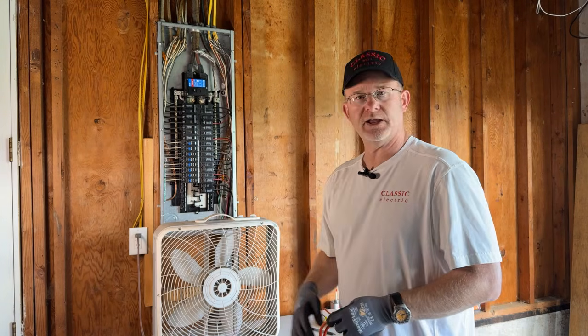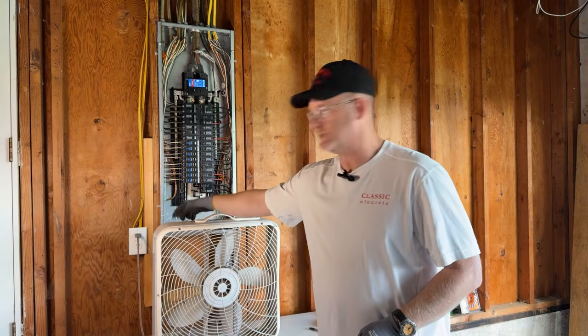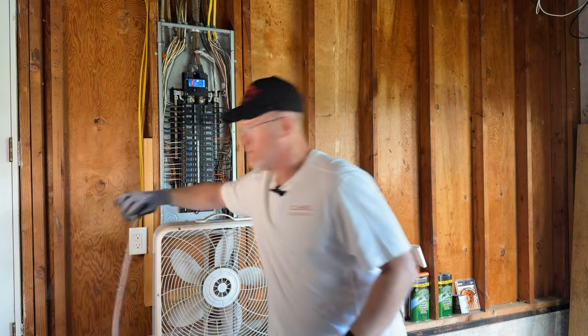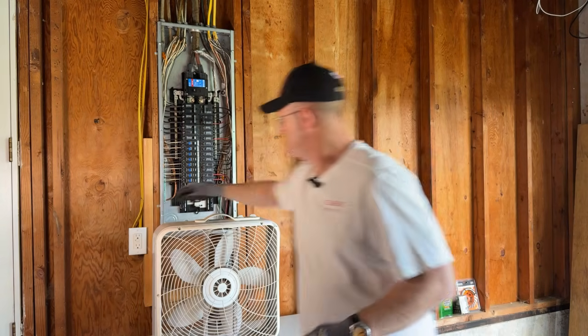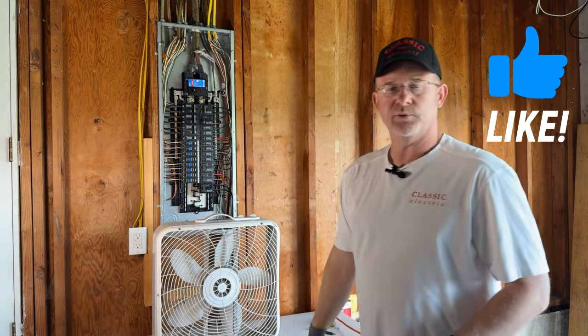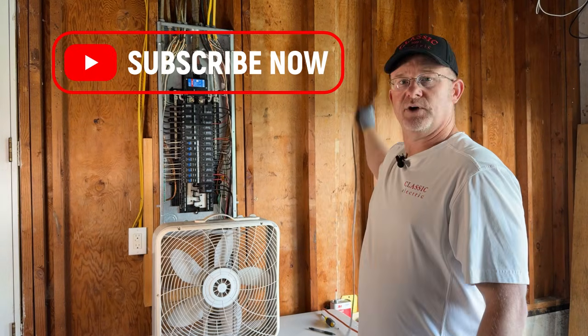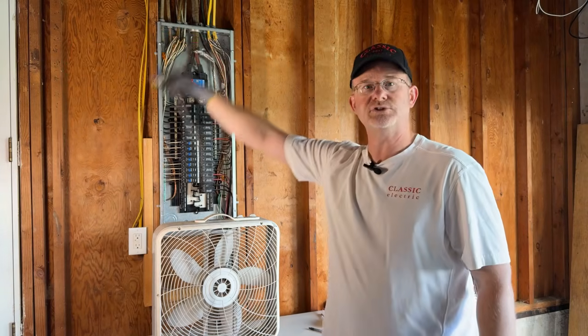But if I can reset it like we are here, one of the best ways to test it is to actually walk over, unplug the item, and if it resets, you're good. But what happens sometimes is the GFI is here in the garage, but it also goes to the front outlet at the front of the house. It also goes to the one at the back.